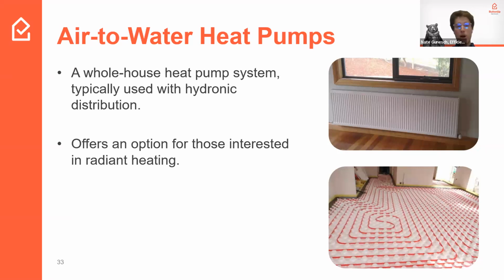Fundamentally, this is the heat pump alternative to a boiler. It's a hydronic system. You're still using heat energy from outside, that's why it's air to water. You collect heat outside with the unit and fans, bring it into the house, and distribute it via hot water instead. These are typically whole house systems, not partial like the ductless heat pumps we discussed. They can be really good for people interested in radiant flooring, which I'll talk about more in a second.